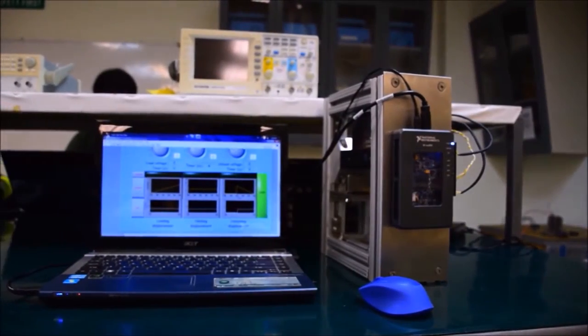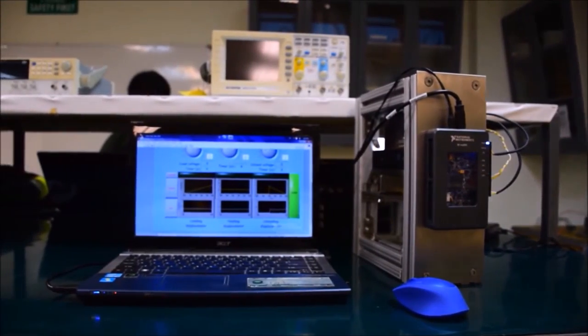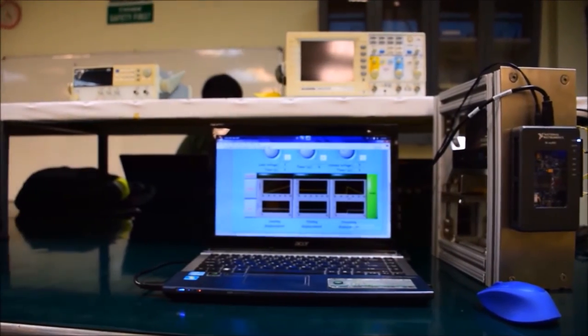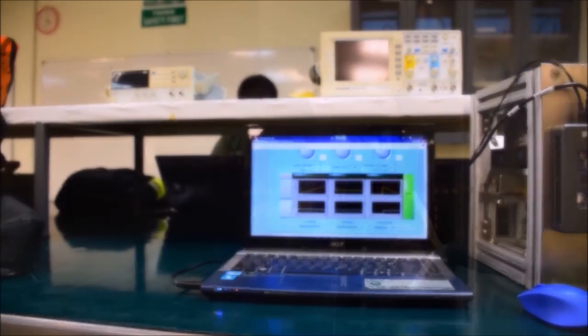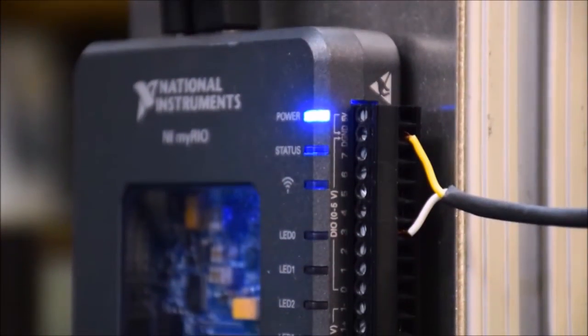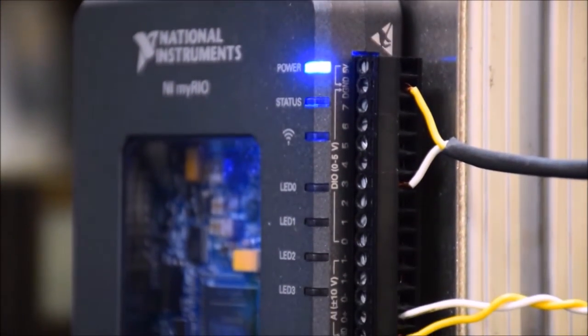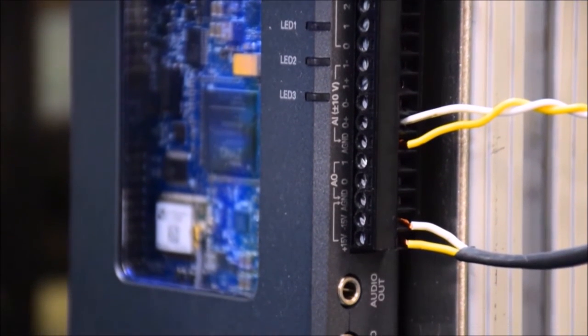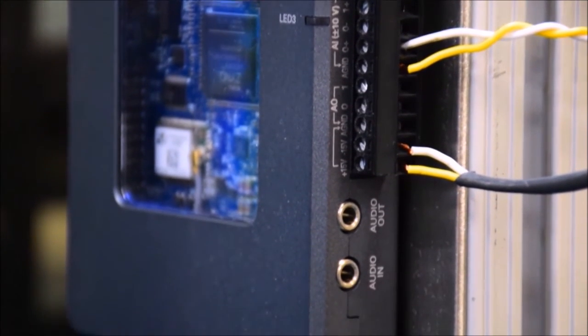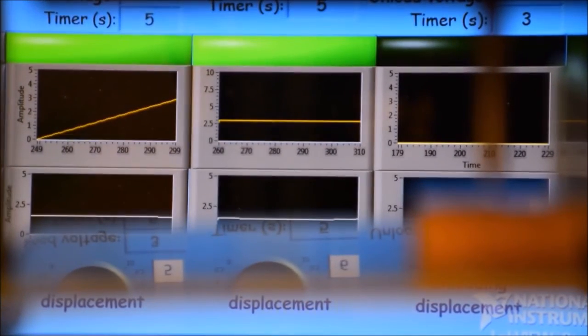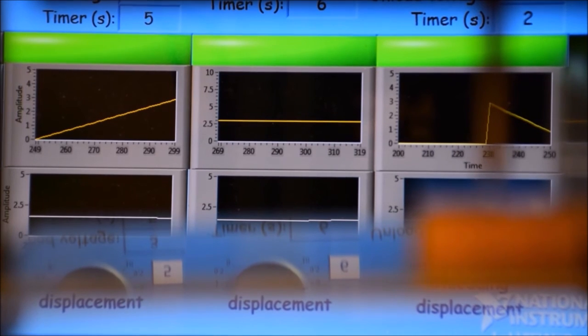The benefits of this system is that it is portable, it reaches the specification of less than 10 kilograms, and it allows industrial people to use it without using an actual size indentation machine. It provides optional choices of algorithms that lets the user perform comparisons of the results.